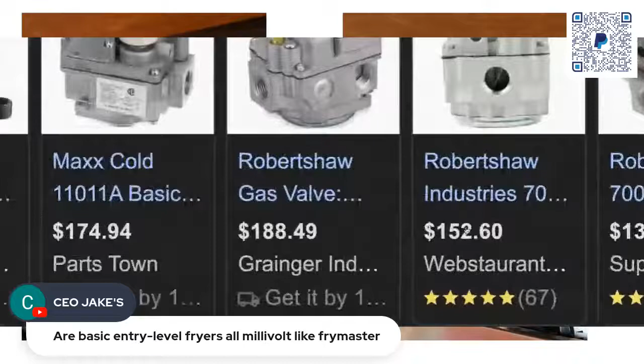Gas fryer valve - these are the valves that your thermopile goes to. This style right here, you see it says millivolt propane combination valve. Actually, this one's been phased out. This valve here has been phased out. They are now going only with the Harper Wyman. So you're only going to see ones like this with the Robertshaw, Harper Wyman. You're not going to see the other style anymore.